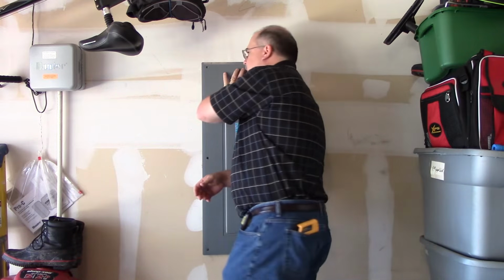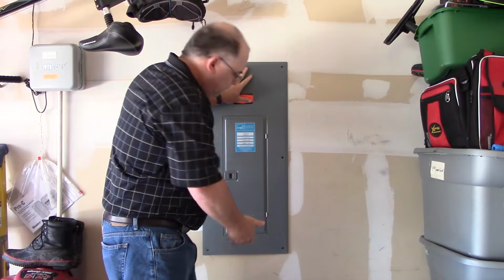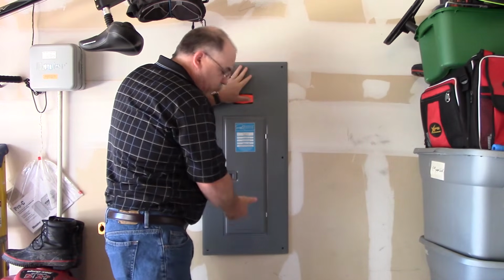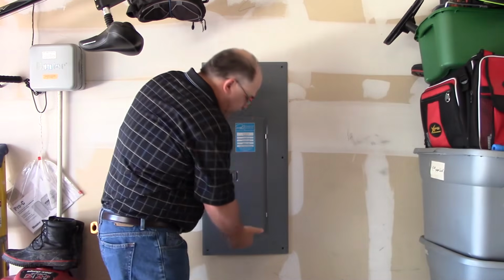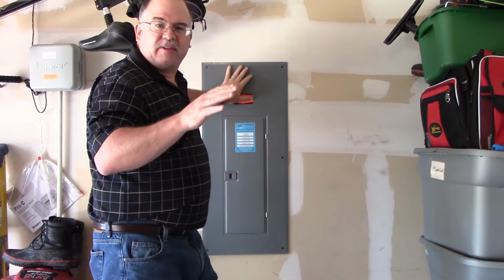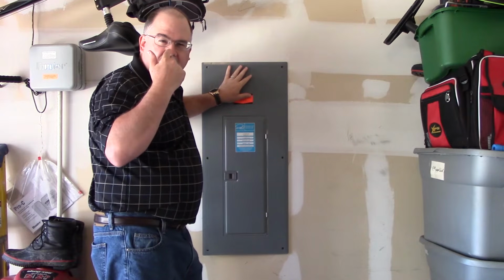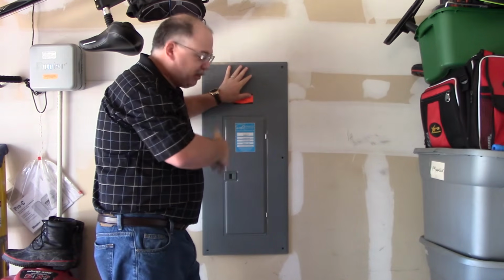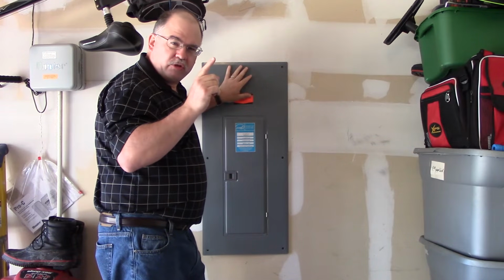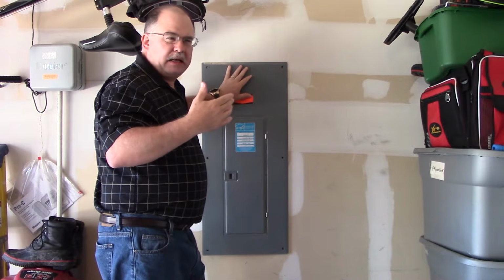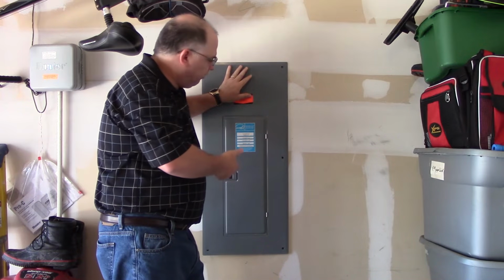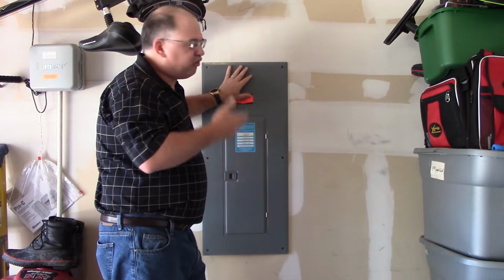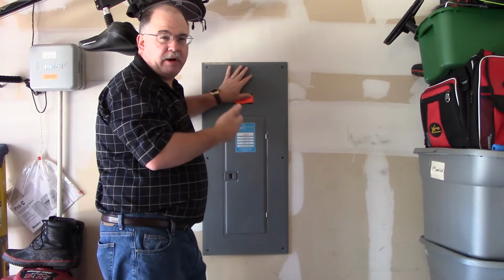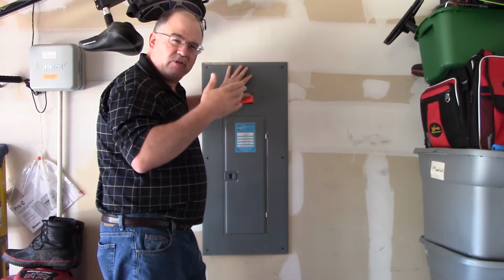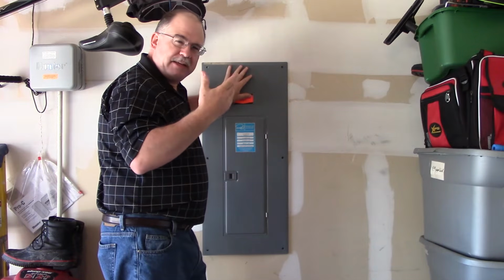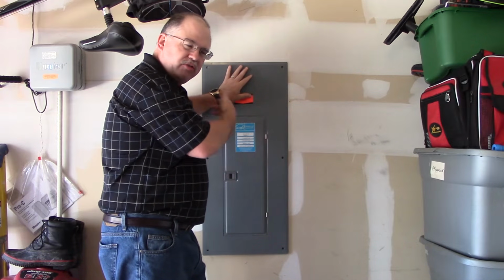Supporting this panel cover, now I'm going to start from the bottom and grip it, and when you push on the top, a lot of times the cover will pop out a little bit on the bottom so you can get your fingers under. Now, a couple things about safety. Safety glasses, and if you're really worried, you already checked the panel, but if you're concerned, you can use gloves. Just make sure they're the right type of gloves, not too baggy, so that you actually have feel, because you don't want to lose hold of this panel cover and have it slip down and damage it, scuff up the wall, or come down and hit the breakers, maybe break a breaker. You want to make sure that you can actually hold it. So you can use gloves if you want. I typically don't because I get more feel, and I've already done all the safety precautions to check this panel.